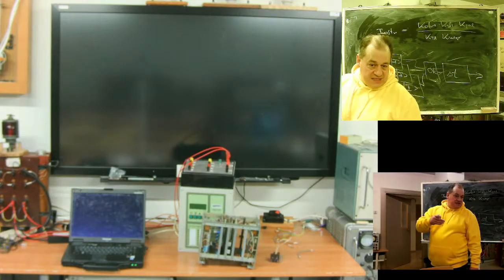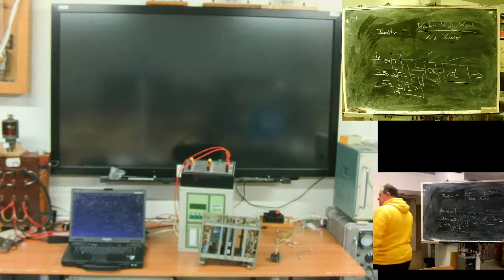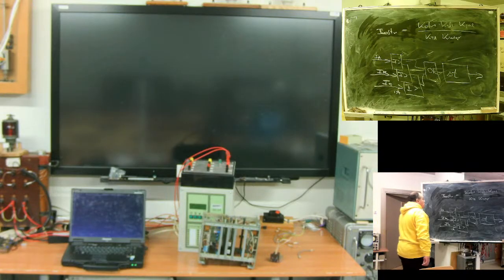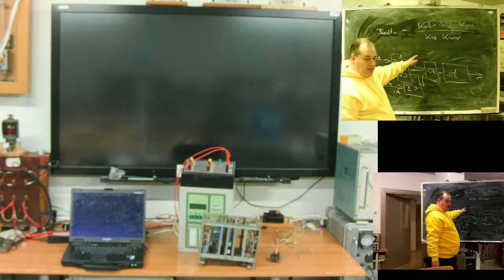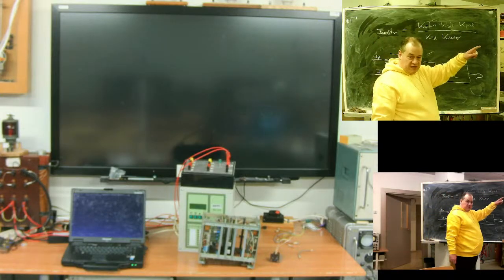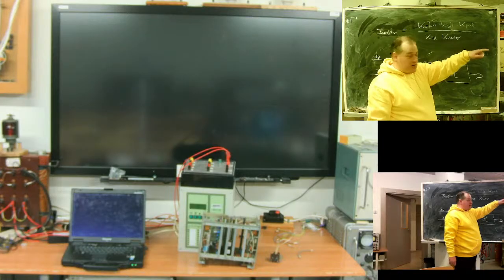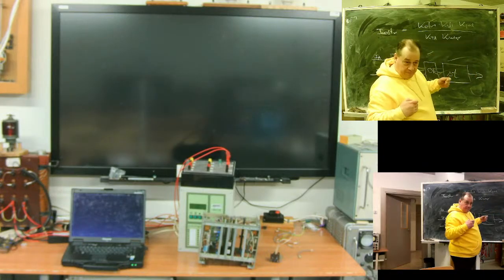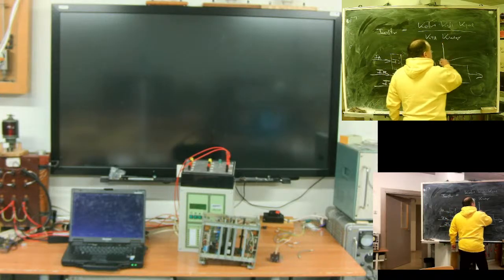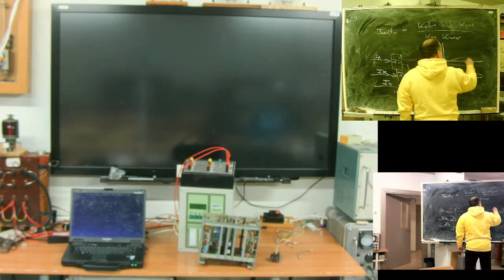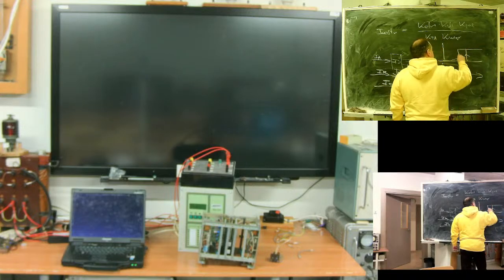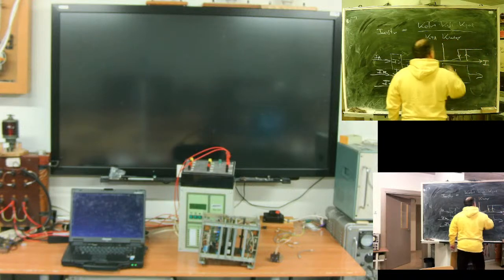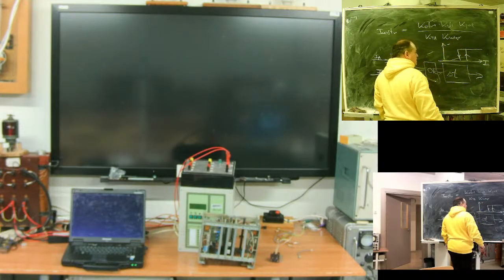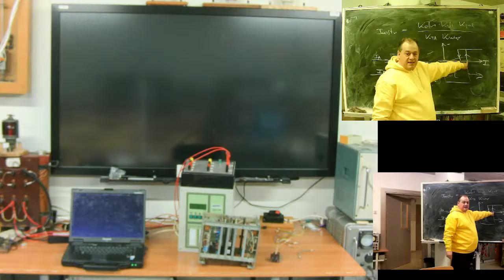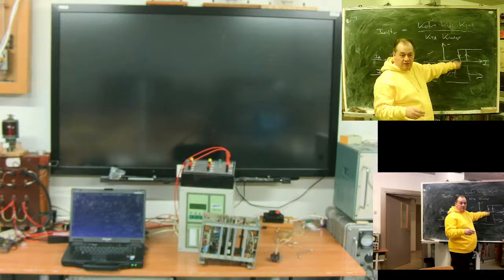When the line is disconnected, the load is disconnected, and current is 0. This zone coordinates, it's a backup for the next line protection. If the next line protection operates, this should return. We should have the current state of the binary signal. Trip current, or let's say on current, should be higher than off.